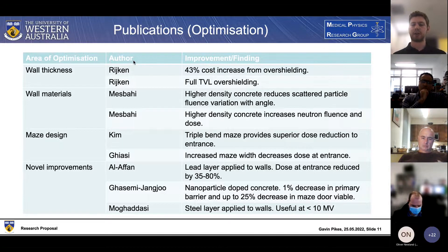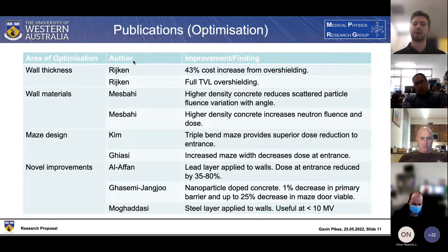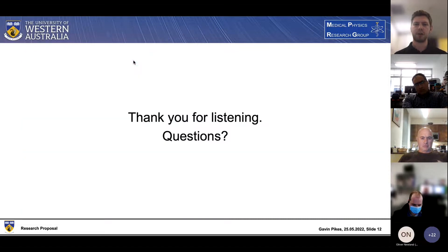Steel layering has also been applied with similar results. Another interesting improvement has been nanoparticle-doped concrete, which resulted in a one percent decrease in primary barrier width as well as up to a 25 percent decrease in maze door width while still maintaining the same shielding capabilities. That's all I really have to say - thank you for listening, are there any questions?